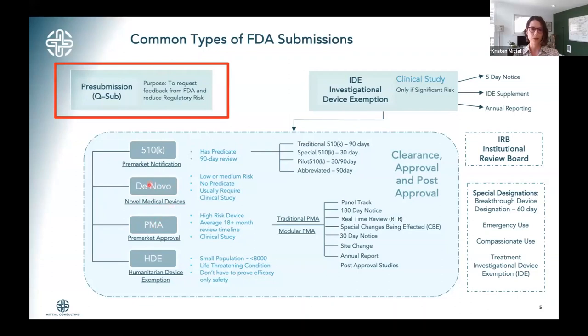This usually does require some sort of clinical study, because there's more need to prove it independently since you're doing less predicating on a previous device. You need to prove independently that your device is safe and effective. So it also takes about a medium amount of work between a 510K and a PMA — definitely more work than a 510K.